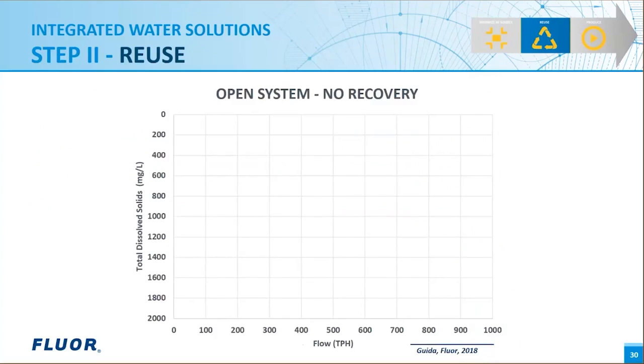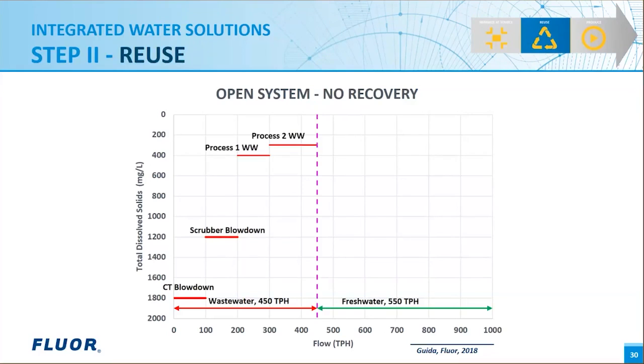This chart shows a typical pinch analysis for a traditional facility with no reuse. The y-axis shows total dissolved solids concentration, one of the primary components of interest for reuse. On the x-axis, flow is presented in tons per hour. On the left side of the graph, we list various wastewater streams, the suppliers: cooling tower blowdown, scrubber blowdown, process 1 wastewater, and process 2 wastewater. On the other side, there are consumers, processes where we need fresh water intake: scrubber makeup, cooling tower makeup, process 1 and process 2 water intake.